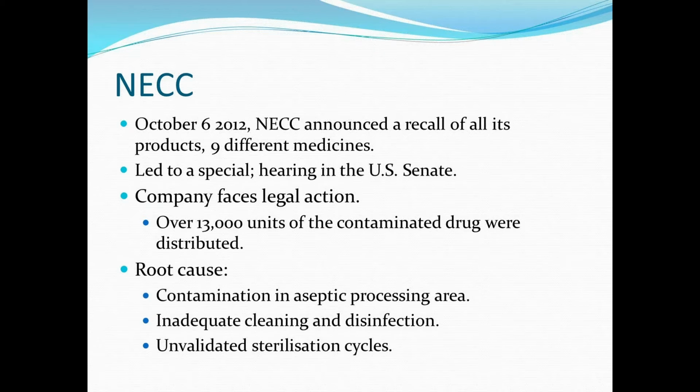The pharmacy was next door to a landfill site, and the air system was bringing in fungal spores, and the HVAC system was not capable, and the HEPA filters were not robust enough to eliminate all of that fungi. So that's an important note, and if ever the question emerges, is there a risk of fungal contamination? This is a very pertinent case study to keep revisiting.